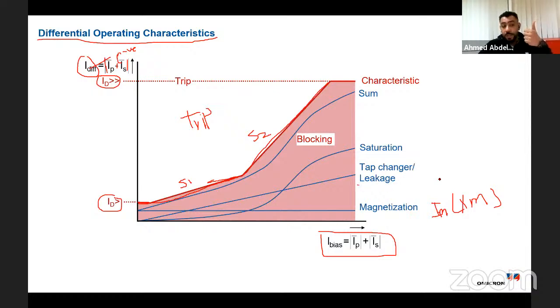The second one is tap changer and leakage. If we remember from the electromagnetic circuit, I have phi, and I have phi sigma 1 and phi sigma 2, these are the stray fluxes or losses. I need to put them in my calculation when I am setting up the relay calculation, because the high voltage side will see phi, the main phi plus phi sigma 1, but the other side will see phi and phi sigma 2. Phi sigma 1 and phi sigma 2 are different.